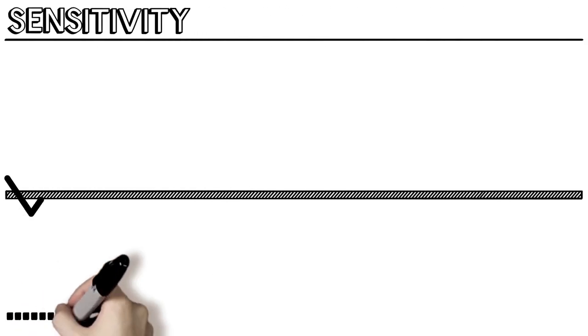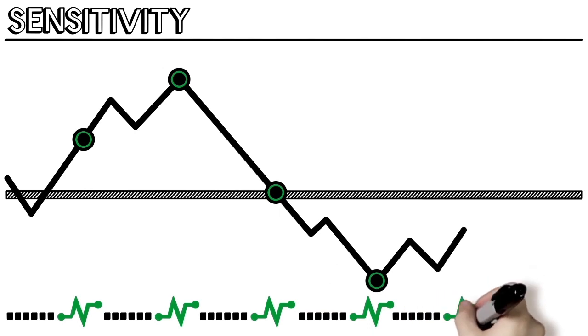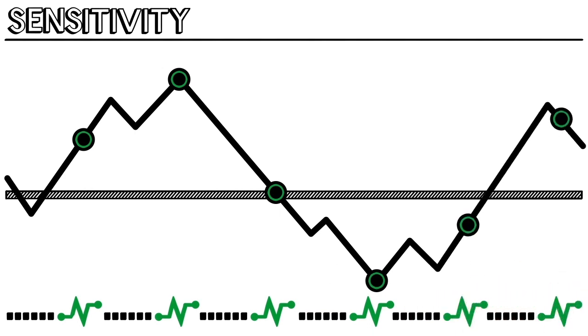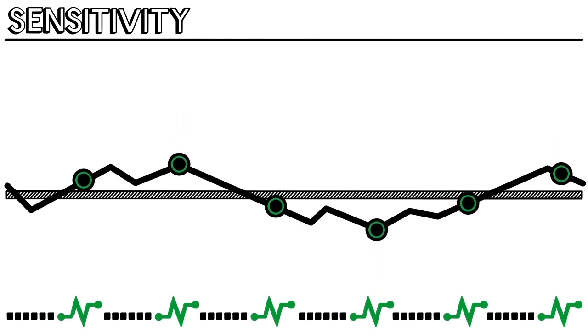Every six hours, TrueCal verifies its own functionality in a number of ways. First, TrueCal measures sensitivity by sending an electrical pulse through the sensor. The current sensitivity is compared to the last gas calibration, and this difference is used to actively adjust the sensor's output to compensate for the change. As humidity, temperature, and pressure change the sensor's sensitivity, it is detected and corrected for by TrueCal.